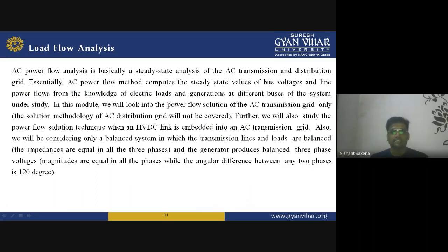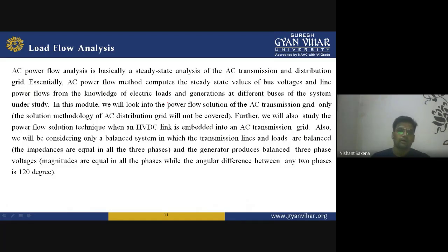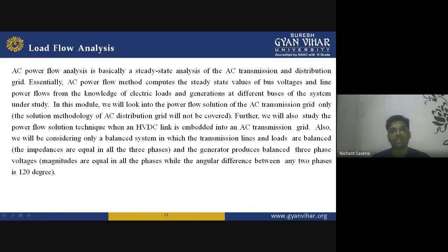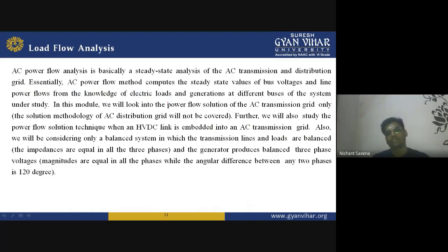Basically the load flow analysis is nothing but the determination of voltages and angle delta at each bus of the power system. With the knowledge of these voltage and delta, we will be able to find out the other parameters — that is the power flow from one end to another — along with the losses of the transmission lines. So by just the determination of voltages and angles at each bus, we will be able to find out all other parameters.